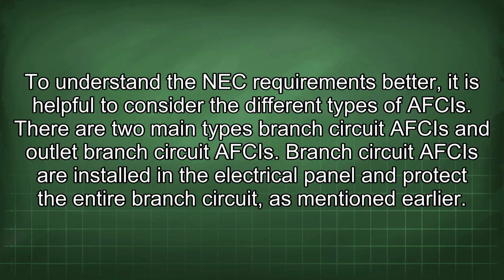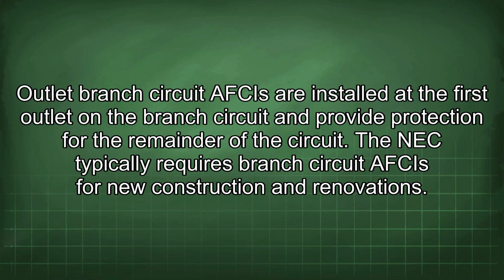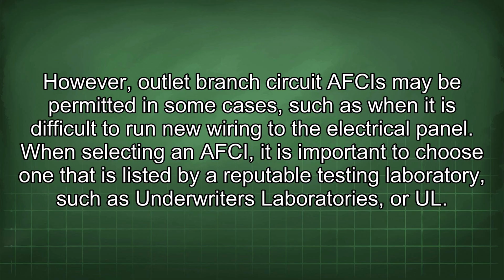To understand the NEC requirements better, it is helpful to consider the different types of AFCIs. There are two main types: branch circuit AFCIs and outlet branch circuit AFCIs. Branch circuit AFCIs are installed in the electrical panel and protect the entire branch circuit, as mentioned earlier. Outlet branch circuit AFCIs are installed at the first outlet on the branch circuit and provide protection for the remainder of the circuit. The NEC typically requires branch circuit AFCIs for new construction and renovations. However, outlet branch circuit AFCIs may be permitted in some cases, such as when it is difficult to run new wiring to the electrical panel.